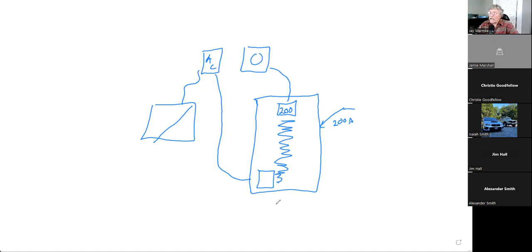But the NEC has said we're going to have what we call the 120% rule. And what that means is you can actually feed that bus bar with 120% of its rating. Well, 120% of 200 amps is 240. So I could actually come in here with a 40 amp breaker from my array. But if I do that, I've got to locate the breaker as far away from the main disconnect as possible.